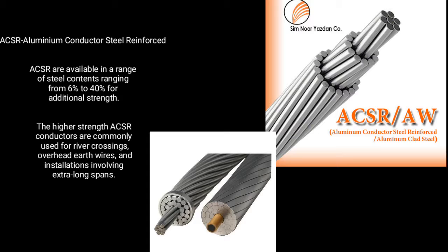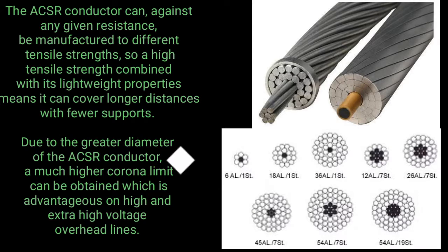ACSR – Aluminium Conductor Steel Reinforced – is available in a range of steel contents ranging from 6% to 40% for additional strength. The high-strength ACSR conductors are commonly used for river crossings, overhead wires, and installations involving extra long spans.